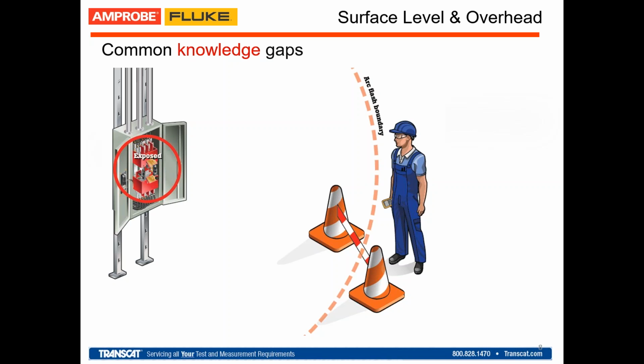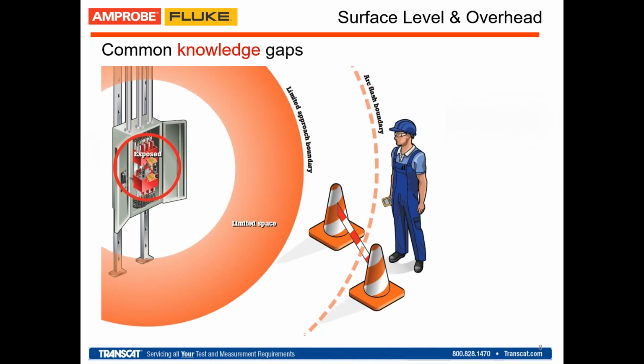Typically, customers are required not to pass the arc flash boundary unless they have PPE and test and measurement equipment that fulfills the categories of voltage protection. Now, the closer they get, they reach the limited approach boundary, which is where you move towards the energized and exposed equipment, and you'll find this boundary, right? It is possible at this point that you are exposed to a shock hazard, so accident probabilities increase dramatically, with arc flashes, if you get close to this area.